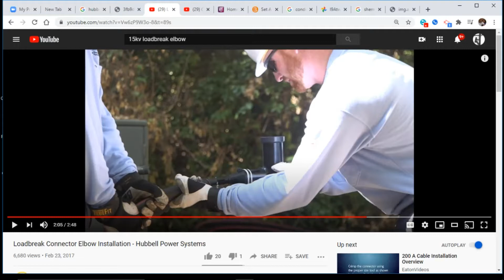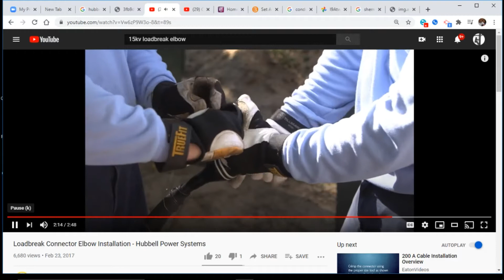Wipe off excess lubricant that may form at the bottom of the elbow. Hand thread the probe into the lug to avoid cross threading. Once the probe has been properly started, now you see this tool that he's using right here. Use the supplied wrench to fully tighten the probe into the lug. The probe will be fully mated.